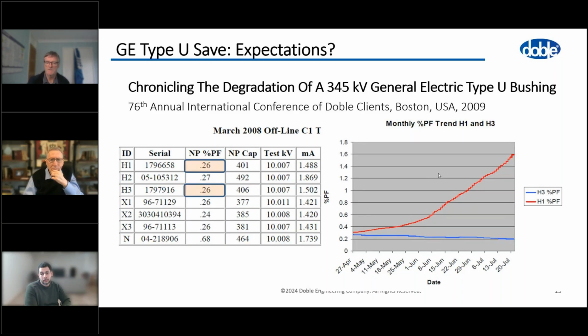So there are some differences when you make a measurement online, because once your transformer is energized and your bushing's at an elevated voltage, the insulation itself is no longer at 10 kV or 12 kV as in an offline test. And that online insulation is now at, say, hundreds of kV. And an effect called the Garton effect kicks in, and that can change the power factor that you see. In this case, this is unlikely to be the cause, because the two bushings, H1 and H3, started very similar. And for some reason, H3 was quite content with where it was, and H1 decided to get upset.